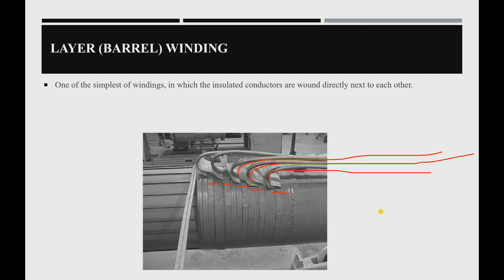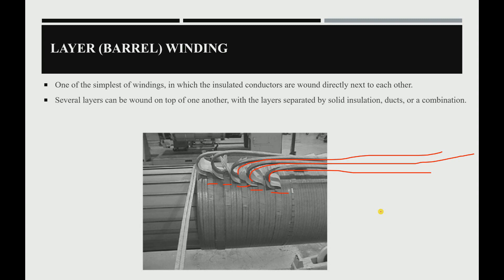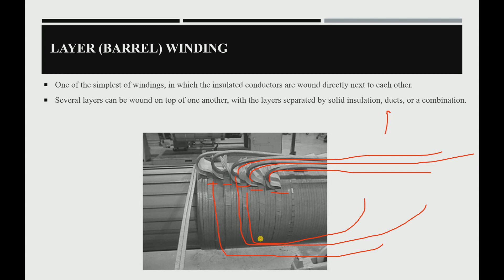The layer winding is one of the simplest winding types, in which insulated conductors are wound directly next to each other. Several layers can be wound on top of one another, separated by solid insulation, ducts, or a combination of both. In oil transformers, ducts allow oil to flow through the windings, helping to cool them down since the windings generate a high amount of heat.